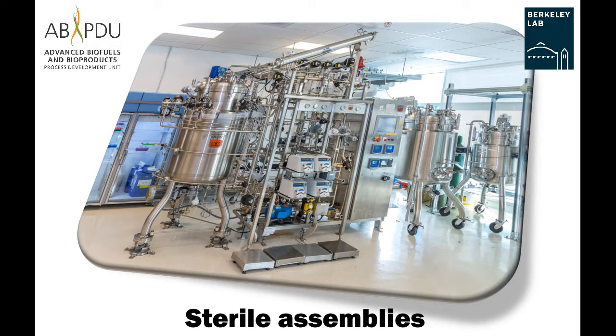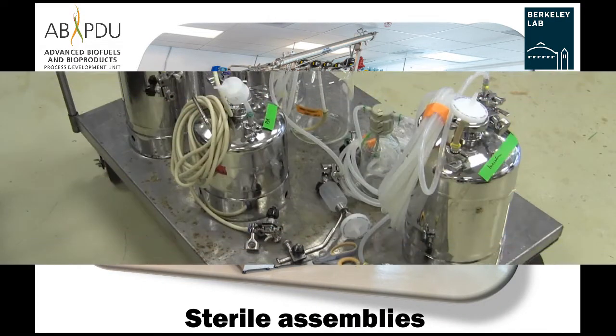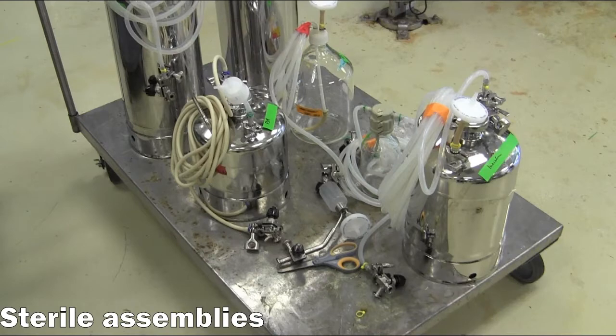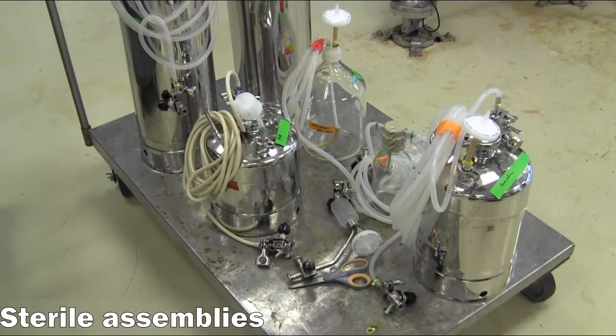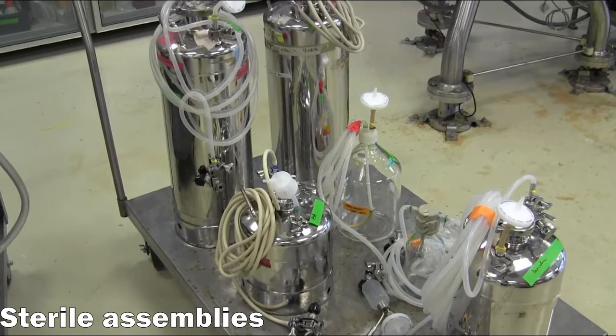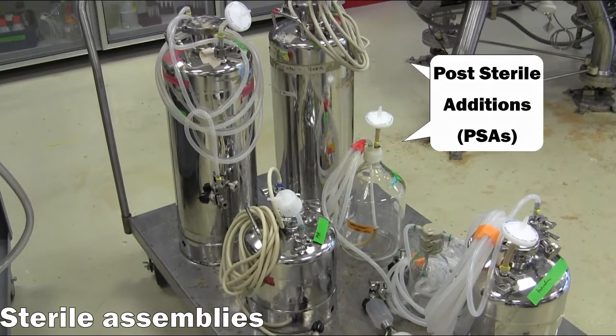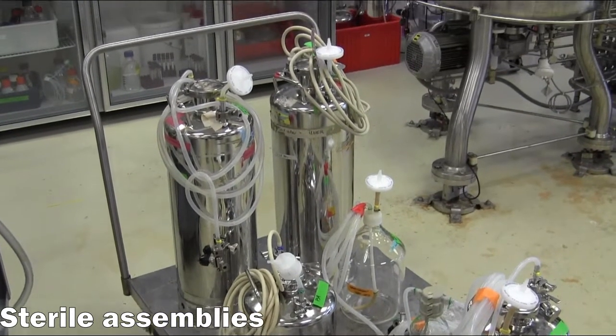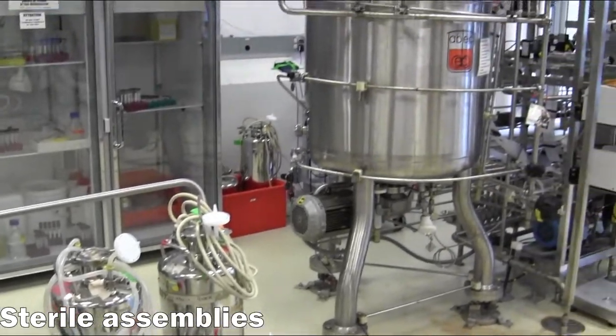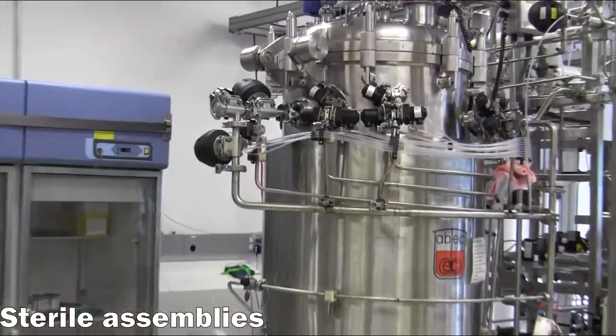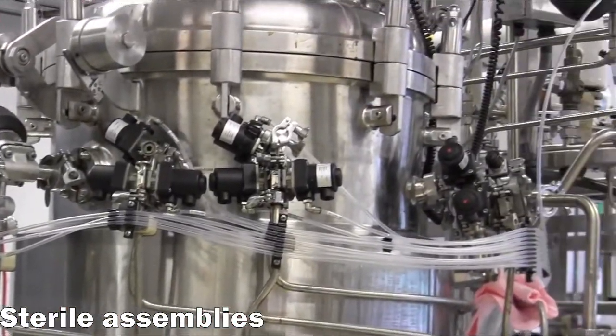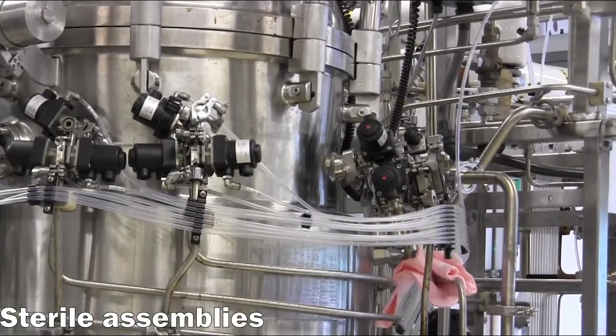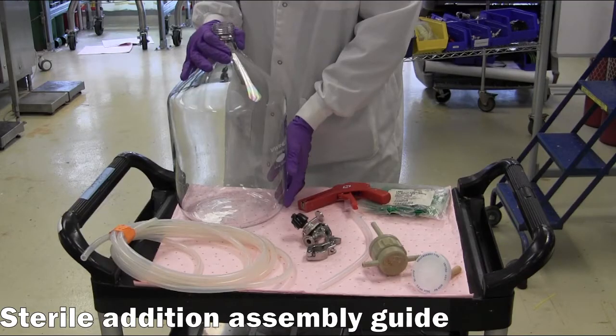Sterile assemblies. Sterile assembly vessels are used for corrective agents like antifoam, inoculum, acids and bases, or any media component that must be sterilized separately. For each assembly, use a length of appropriately sized tubing made of a compatible material long enough to run from the assembly vessel through the pump and to the desired additive port on the fermenter. Here's a quick guide on how to set up sterile assembly bottles.